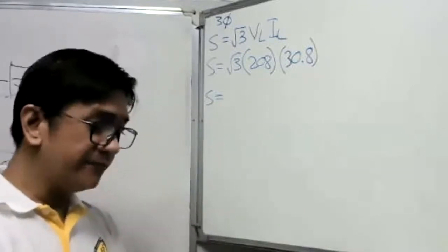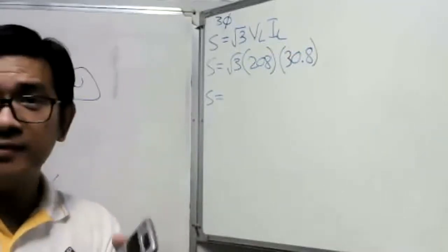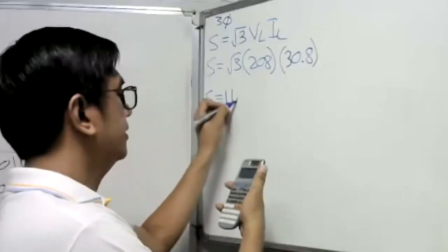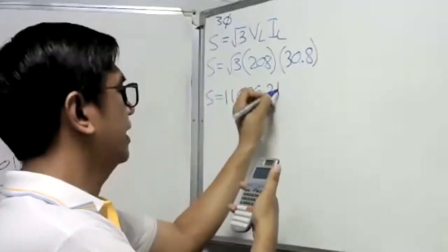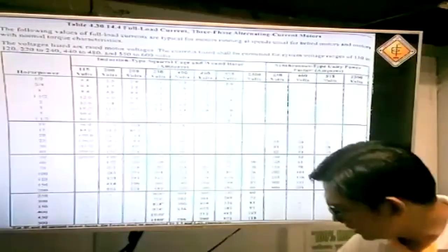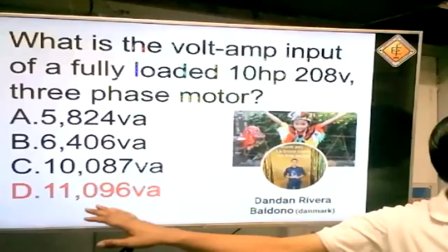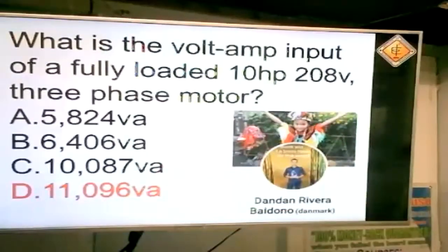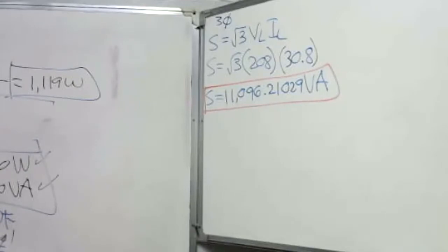So yung S natin, that's equal to square root of 3. Ano ang load voltage natin? Line to line voltage natin ay 208 volts. Ano ang kuryente natin? Yung kanina yung nasa table natin ay 30.8. 30.8 amperes. So, i-compute po natin mga kawerpa. Using app. Mag-compute na po kayo dyan. Use your calculator. Sa square root of 3 times 208 times 30.8 equals. Ayun, ang aking sagot ay 11,096.21029. Tama ba mga kawerpa? Nakita ba partner? Makasabihin nila may daya eh. Nagko-compute din po ako dito. Sana kayo din. Nagko-compute dyan para masanay kayo. So ang sagot ko po ay 11,096.21029. Sinulat ko na ng buo. Volt ampere. Mga kawerpa. Yun ang aking sagot kay Dandan. Ayun. Letter D. Tama yung sagot natin.